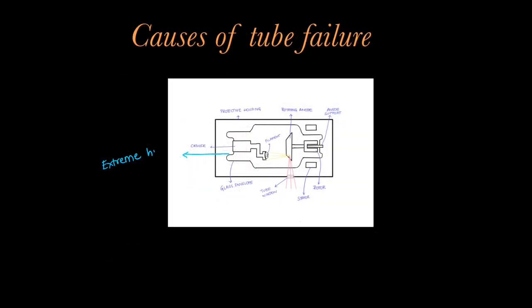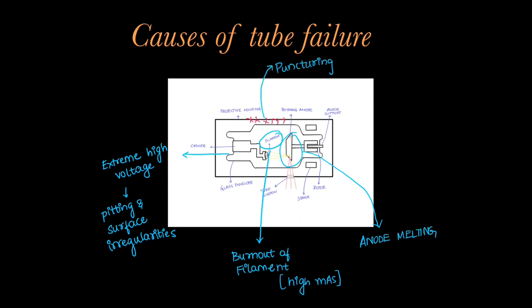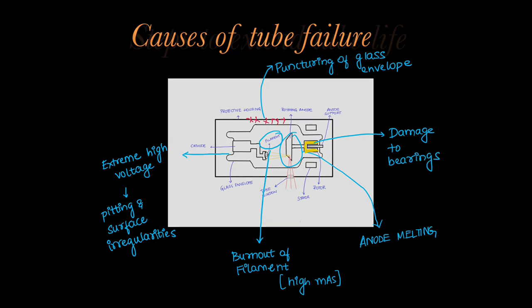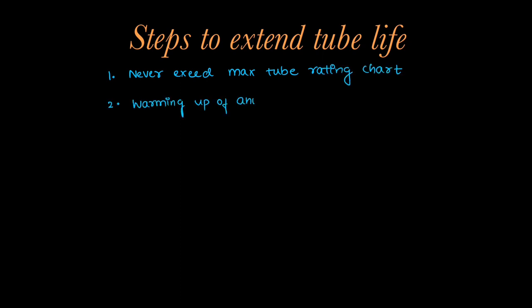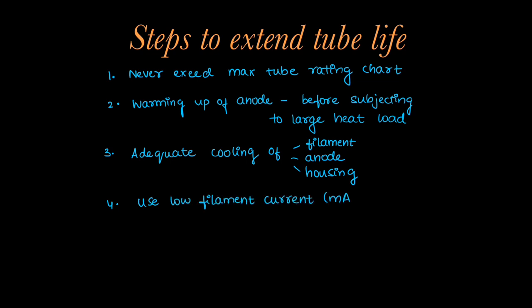Now we will learn about the causes of tube failure. Extreme high voltage in the cathode can cause pitting or irregularity of the surface. The filament can burn out at high filament currents. Anode melting can occur due to the electron beam. There can be puncturing of the glass envelope, and damage to the bearings of the rotating anode. To extend tube life: never exceed the maximum tube rating chart values of KVP and MAS; warm up the anode before subjecting it to a large heat load; ensure adequate cooling of the filament, anode, and housing before the next exposure; use low filament current for each exposure; and do not run the anode unnecessarily.